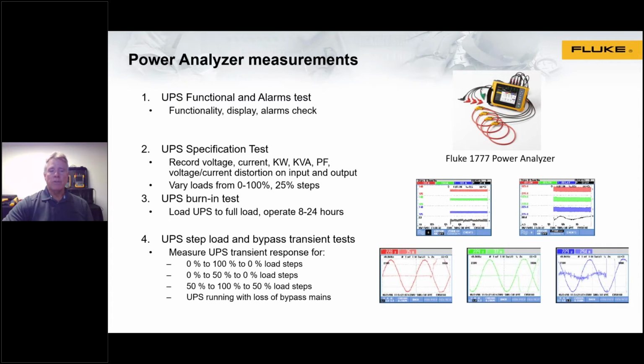The power analyzer needs to be able to, as is evidenced by the waveforms over here on the right, observe and watch for that transient response even as full load current is applied. And as you can see in the example over here for the 3 phases in question, the voltage waveforms hardly vary at all, even with a big step increase in current. So that's really what you're looking for. You need to be able to capture things down to much faster than a single line cycle to look for that transient response.